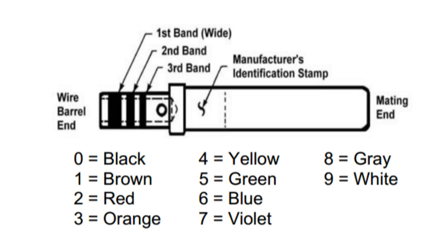Military contacts are identified by a series of three color bands, each representing a specific digit, known as the BIN, or basic identification number, code. The color bands are read from the wire barrel end of the contact or widest color band, then towards the mating end of the contact.